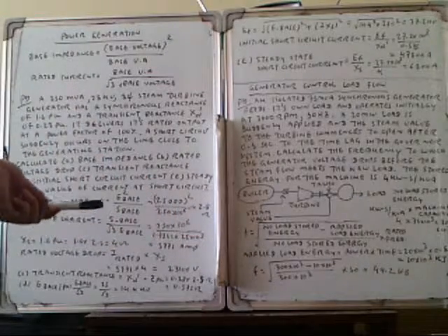The normal stored energy is calculated as: stored energy constant (4 kW·s/kVA) multiplied by machine capacity. The machine capacity is 75 MVA = 75 × 10³ kVA, so normal stored energy = 4 × 75 × 10³ = 300 × 10³ kW·s.